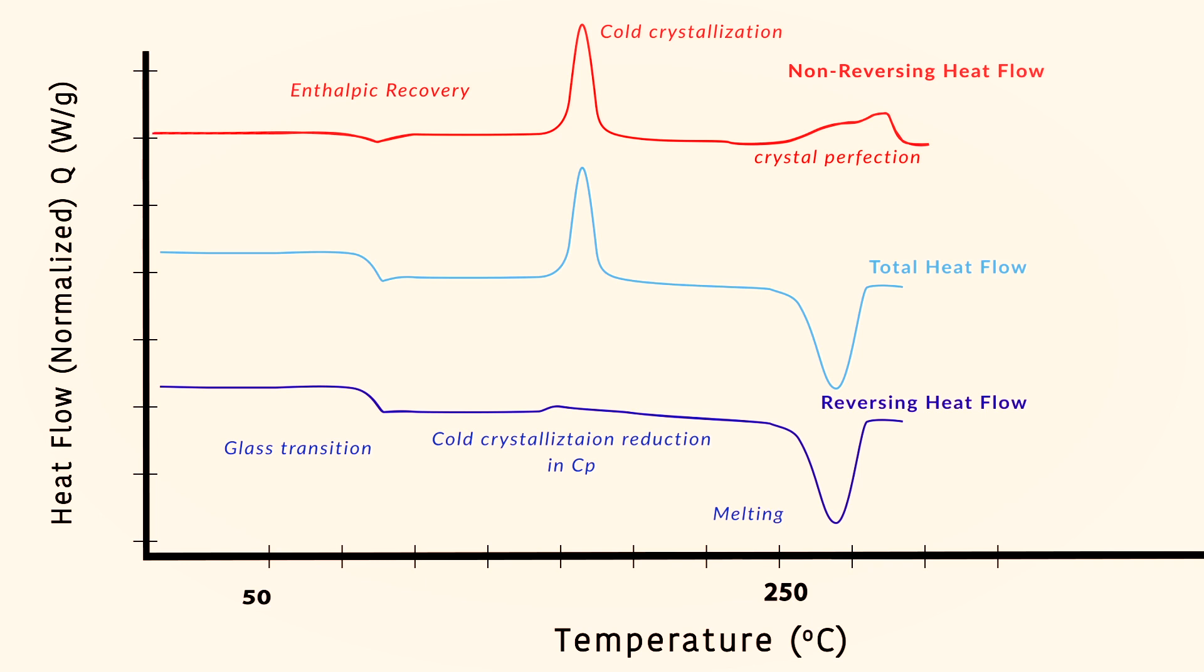Now let's look at the non-reversing signal. As we begin to heat the sample, we can see a small blip in the curve, which is the enthalpy recovery that we discussed in the previous sessions. In the conventional DSC, the glass transition and the enthalpy recovery both overlapped and we could not resolve these two components separately. As we continue to heat the sample, cold crystallization of the amorphous PET material is seen, and this curve continues to have an exothermic reaction, as can be seen through the crystal perfection, which happens right near the melting point.